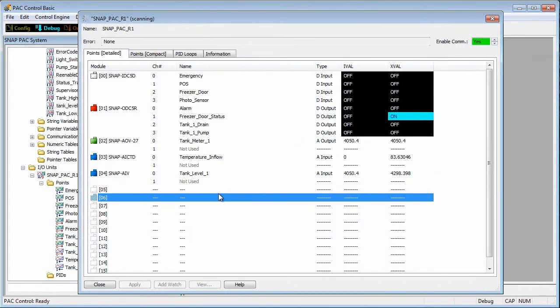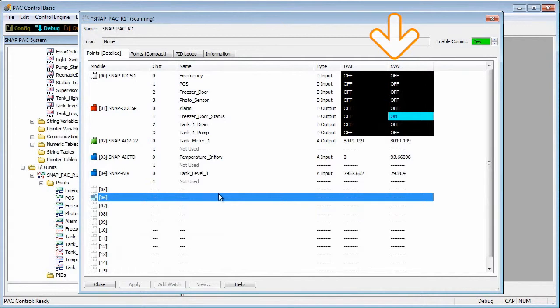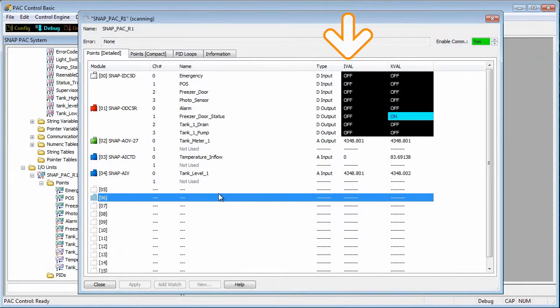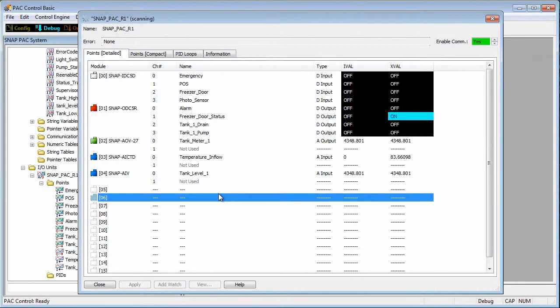You probably noticed there are two columns of values. The XVAL, which stands for external value, is the value of the hardware, the I/O, or inputs and outputs. IVAL stands for internal value. This is the software value in the control engine. Having these separate values is useful for software simulation and debugging, and also for forcing outputs.